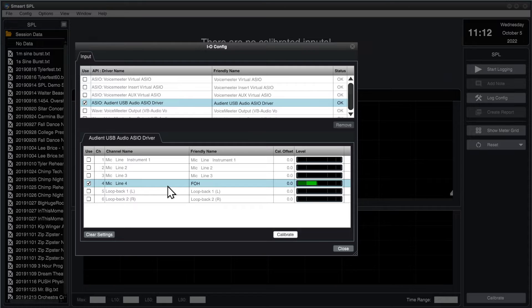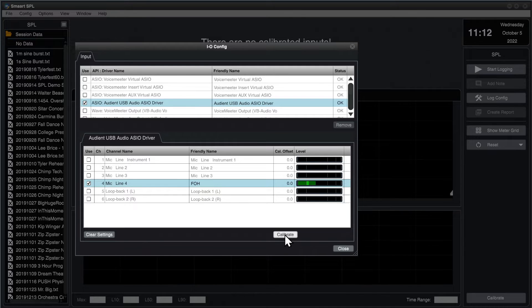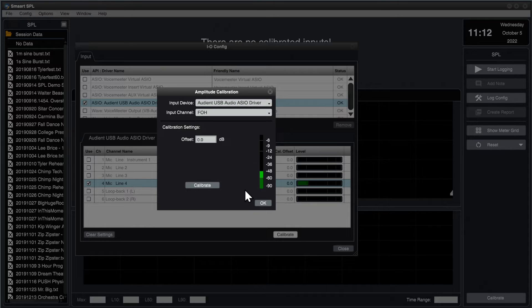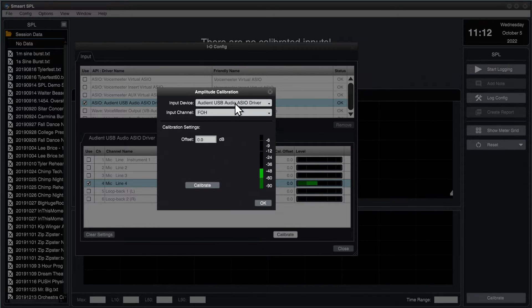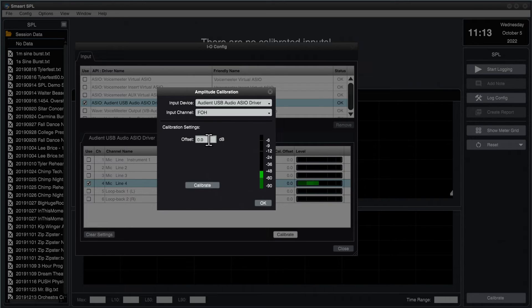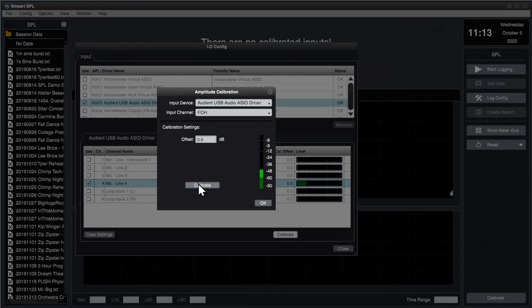So now we need to calibrate our input. I'm going to select the desired input and click the Calibrate button. This brings up the amplitude calibration dialog. Again, at the top of the window, I have the ability to choose the device and input channel that I want to use. And then I can see the current offset, which is 0. I can see a level meter and a calibrate button.